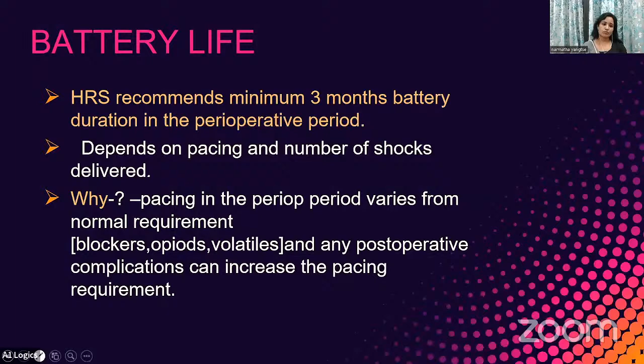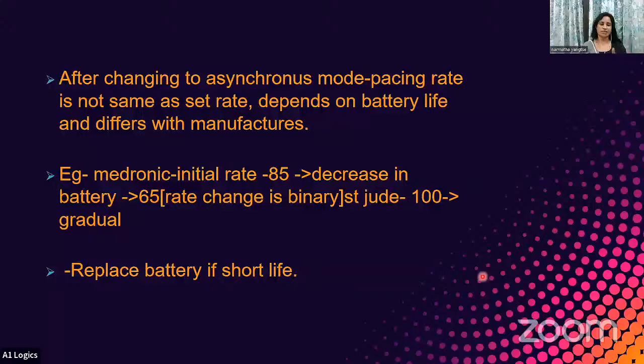Another important thing is, while we are changing the pacemaker to the asynchronous mode, the set pacing rate is not the same as the delivered rate when the battery life is very low. It varies with the manufacturers. For example, if it is a Medtronic and the initial set rate is 85, if the battery life is very low, it will reduce in a binary fashion, that is, from 85 it will reduce to 65. If it is a St. Jude, their basic rate is usually 100, and it will reduce in a stepwise pattern. So that is why a minimum of 3 months of battery life should be there. Otherwise, you have to change the battery before taking up the patient for an elective surgery.